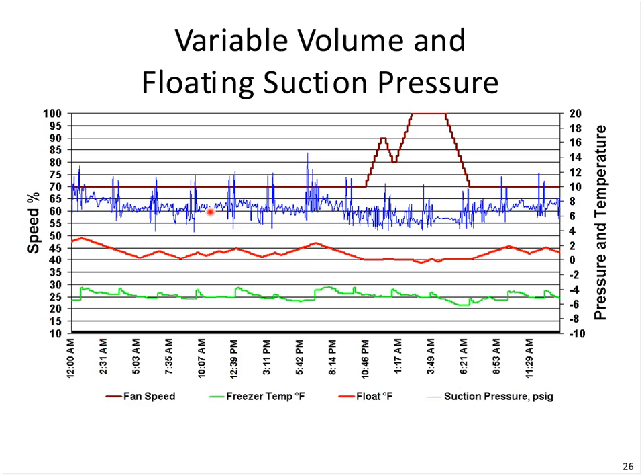This line here is our suction pressure. And notice these little jagged lines here are the defrost cycle that's taking place every few hours. And then the top line here is the evaporator fan speed, denoted by the percent speed here. Over here we have pressure and temperature. And along the bottom, time, so middle of the morning, middle of the day here, and then back to another day. So we can see the processes. The temperature in the space here is going above the set point.